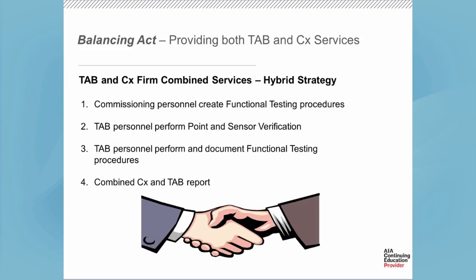In this case, commissioning personnel within the firm create the functional testing procedures, and tab personnel actually perform those instead of the commissioning personnel. So tab personnel perform the point and sensor verification, and then, instead of doing normal test and balance control verification, they perform the functional testing procedures written by the commissioning personnel. This applies primarily to HVAC systems, and potentially some plumbing systems — not electrical, not life safety and things like that. But with respect to HVAC systems, this is a viable option depending on the situation.